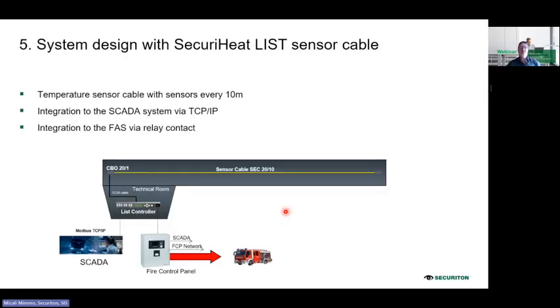We have different possibilities for the design. A very simple design is that you have one cable inside the tunnel. This is connected via a communication cable to a LIST controller, and from the controller you go first with some relay contacts to a fire control panel in order to fulfill the local fire requirements in case of alarm. So you will also get an alarm on the control panel. On the other hand, you can integrate this LIST controller directly into the SCADA system using Modbus TCP/IP, so that the operator is able to get the temperature profile of the tunnel.